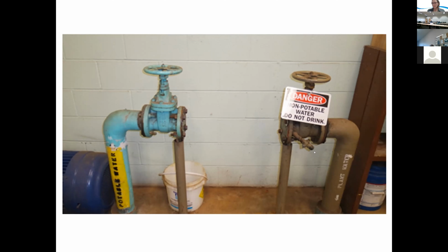And so when you start looking at your recommendations of, well, what should they do here? My recommendation was to weld this blank flange on, make it something different than just spinning 4 bolts to be able to reinstall the device. Later on, as I was talking to people, they said, well, why not just remove the whole valve and then weld a blank flange on there? Then they really couldn't get to it again.